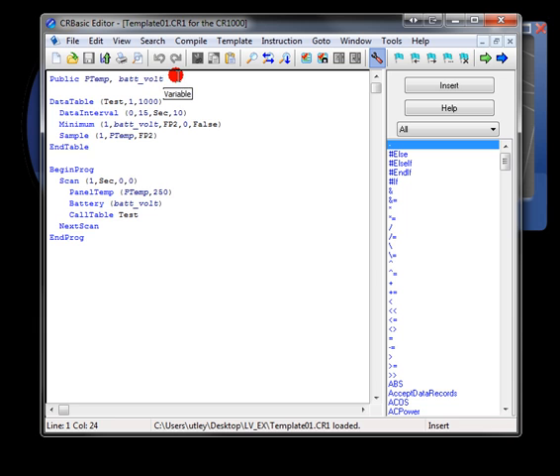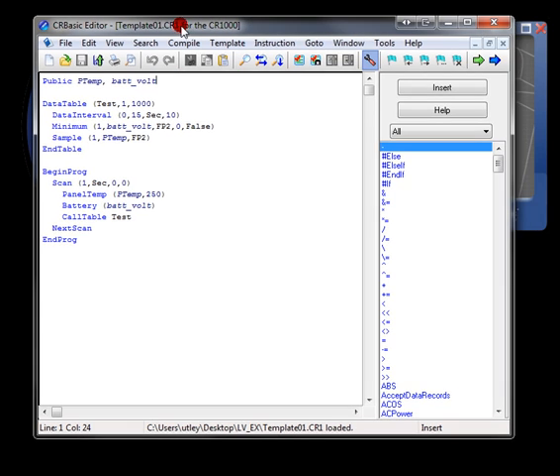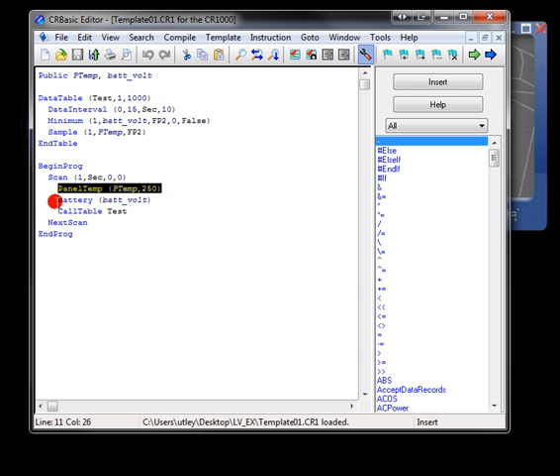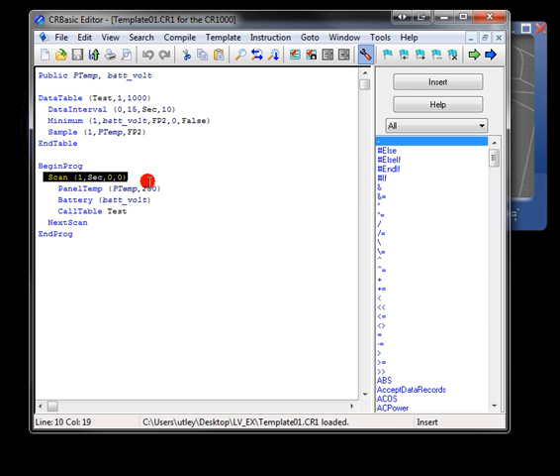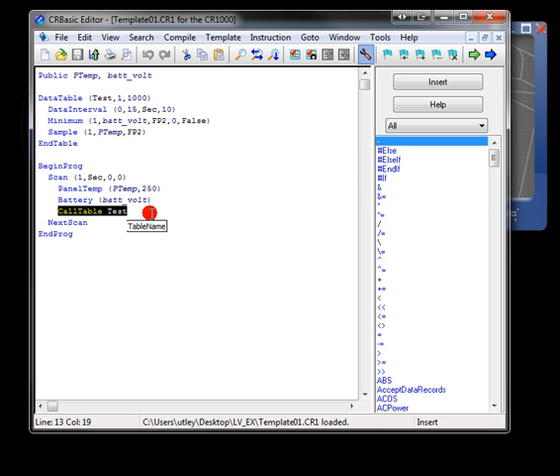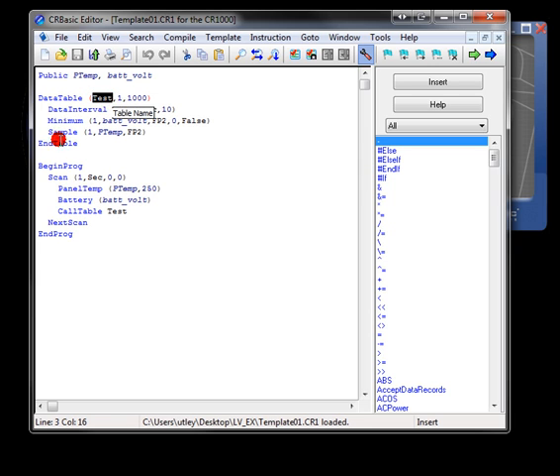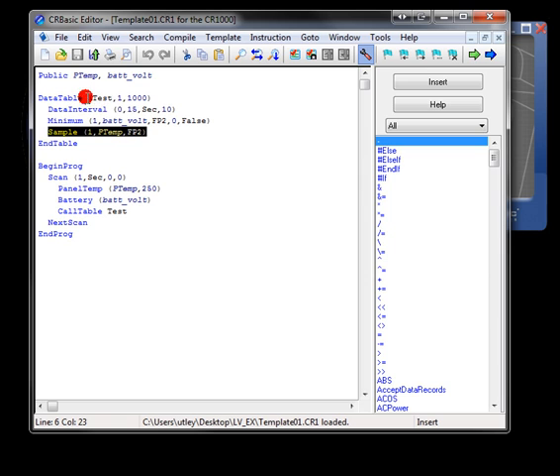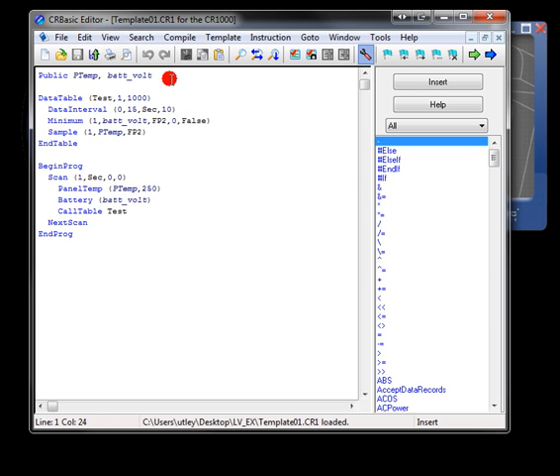I'm starting with the default template presented by the CR Basic Editor. That default program or template measures the panel temperature and battery voltage every one second. It also calls a special type of subroutine called a data table every one second. In this example, the data table is called TEST. TEST will save the minimum battery voltage and the last known panel temperature every 15 seconds.